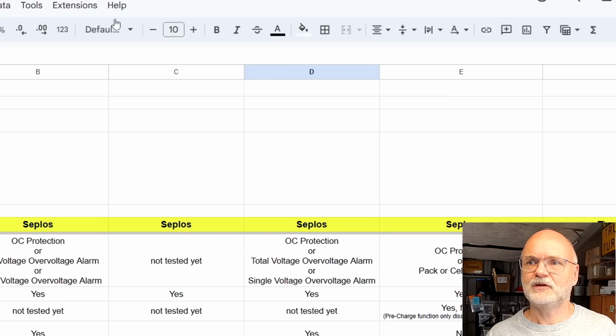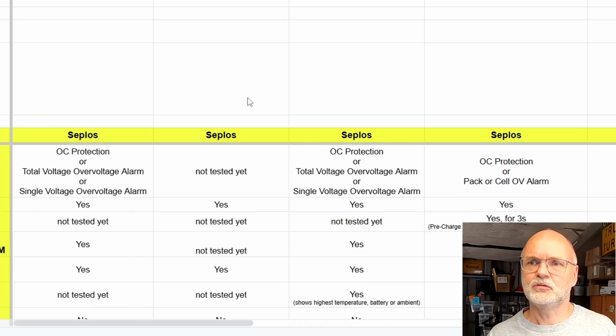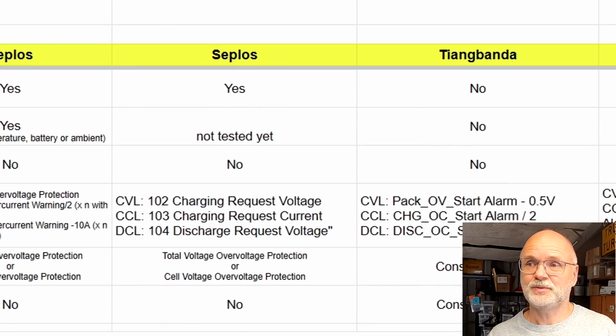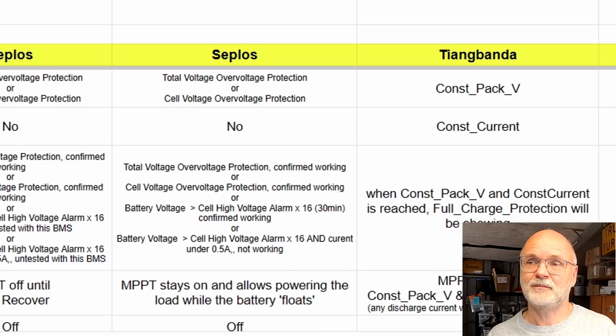For that, we will have a look at the BMS comparison chart. So these two are the first generation BMS with different firmwares, second generation BMS, what we are looking at right now, and the third version BMS. And with the third version BMS, they actually introduced another method to recalibrate to 100%: if the battery voltage is higher than your cell high voltage alarm times 16, for 30 minutes.